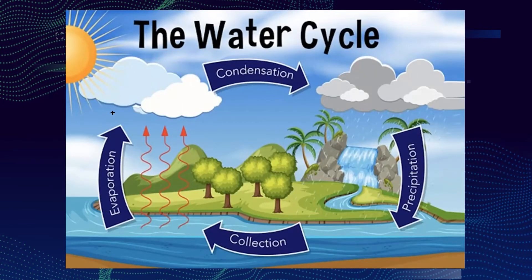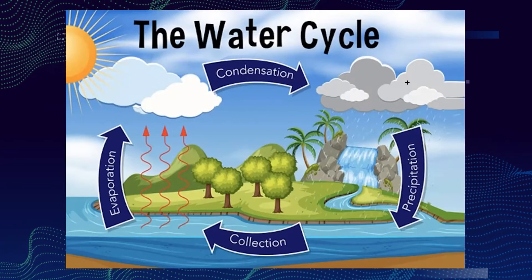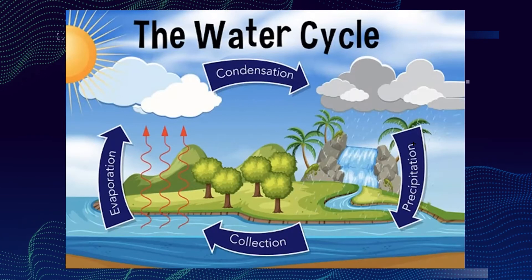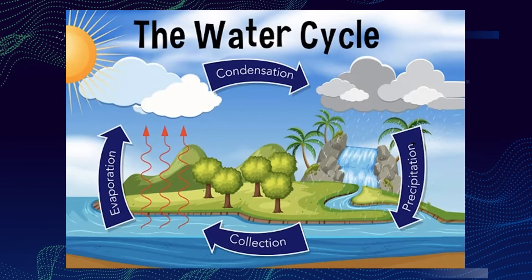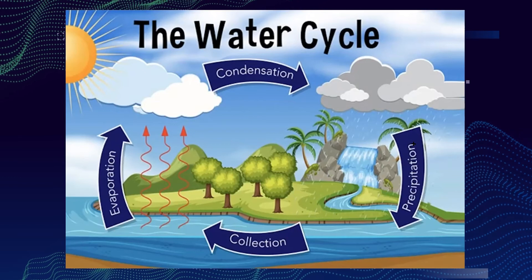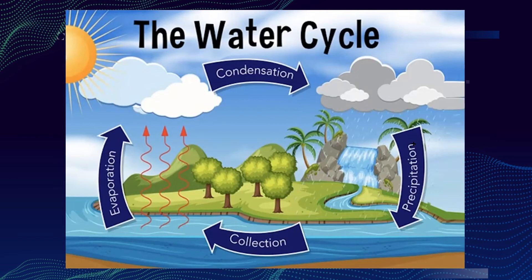In a swimming pool, water evaporates from the pool, and you mechanically condense it with a coil. It precipitates from that coil and dribbles down. Currently it goes to waste, but that's pure distilled water. What's the problem with putting it back into circulation? There's absolutely no problem putting it in, other than some state codes don't allow it — so have your engineer check your state code. But it is distilled water; you eliminate having a refill. Your calcium goes up because when water evaporates, all the minerals stay behind. An indoor pool evaporates roughly its entire volume in a year — the same as an outdoor pool.